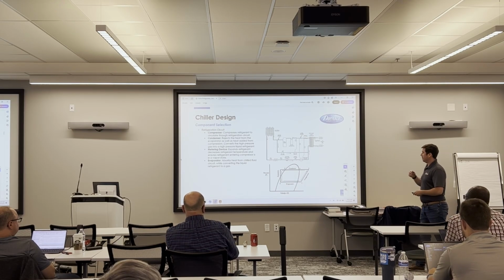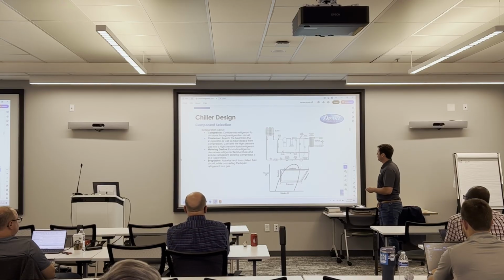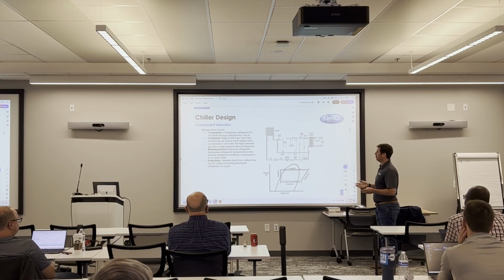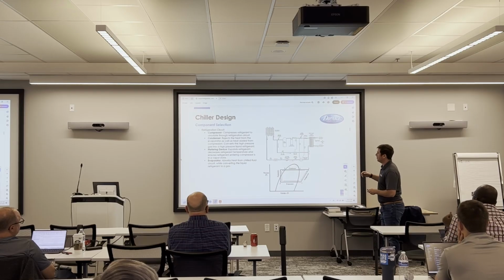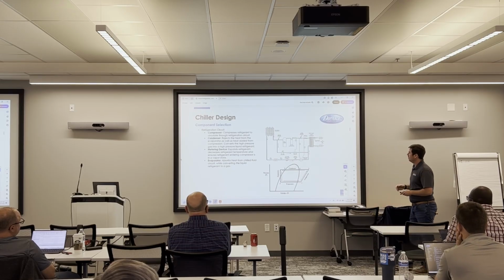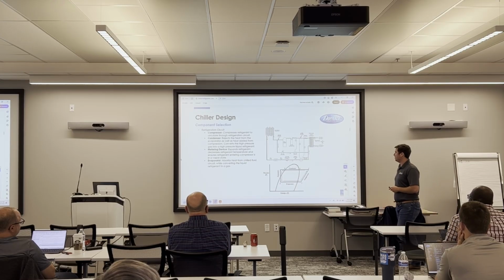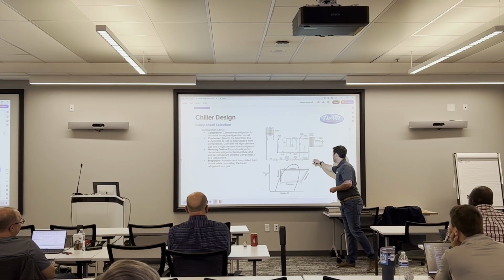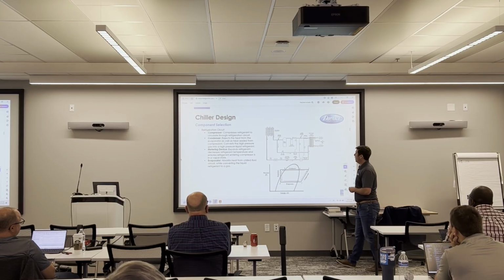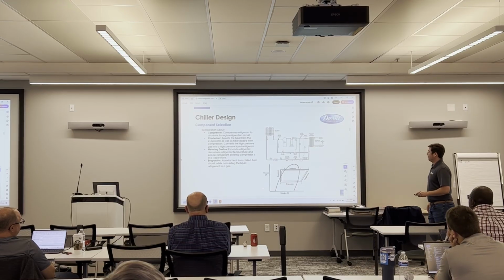So that's your subcooling point right there. These expansion valves do not like to see refrigerant in its gas state. They do not work correctly. So the purpose of the condenser is just to make sure everything coming out of that condenser exists as a liquid. And again, this metering device is the most important component on this circuit, I would say. It's just going to make sure that it's metering the proper amount of refrigerant to get a vapor out of the evaporator. And you can see a different visual down below.